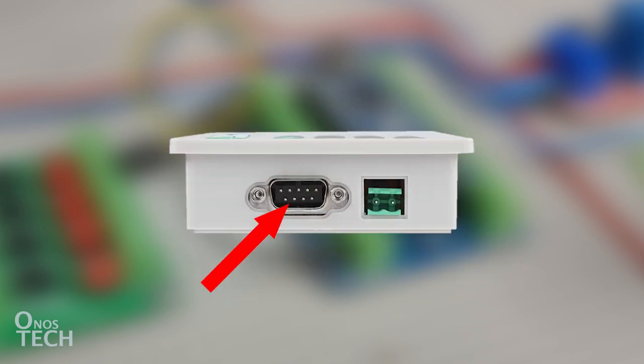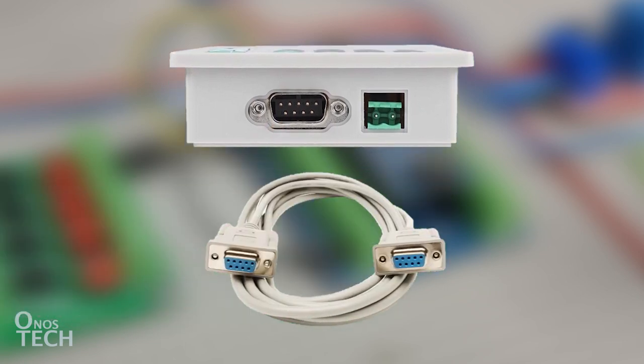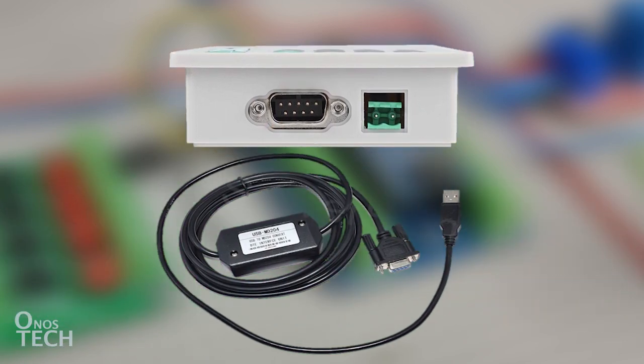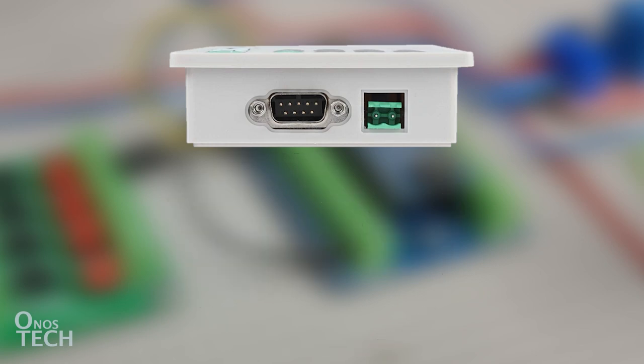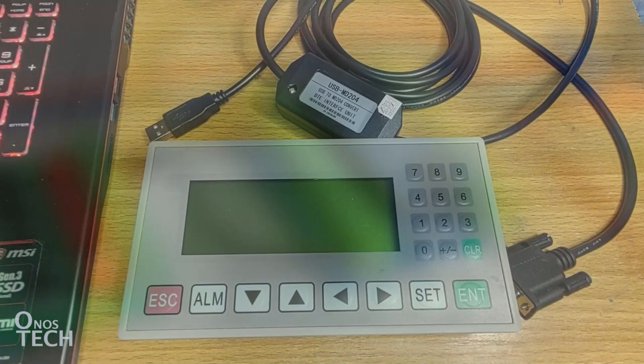The download/com port is connected to a PC serial port using a DB9 serial cable, or the USB port using the USB MD204 cable to download the configuration. See the link in the description. The same port also communicates with the PLC. It requires a 24-volt DC power supply to operate.